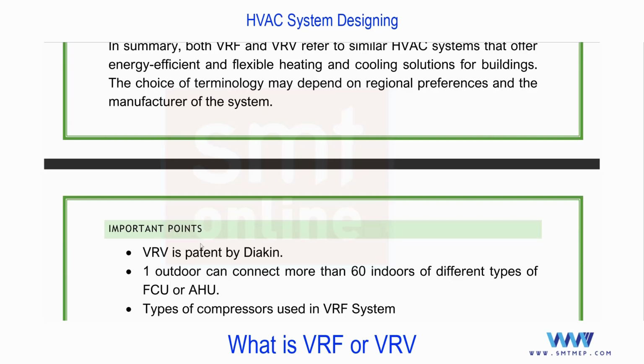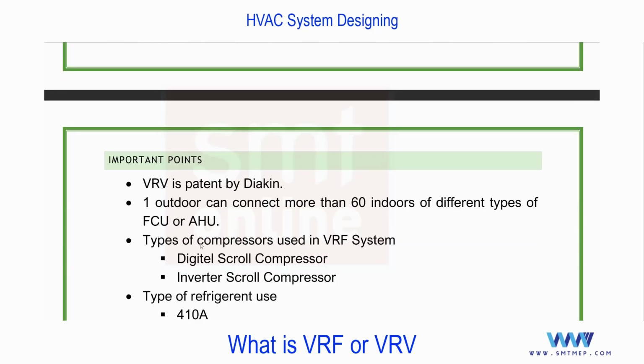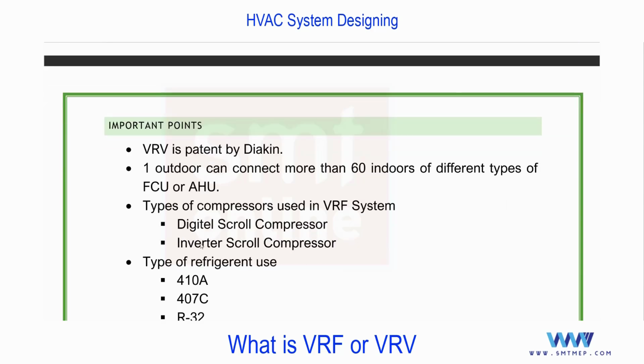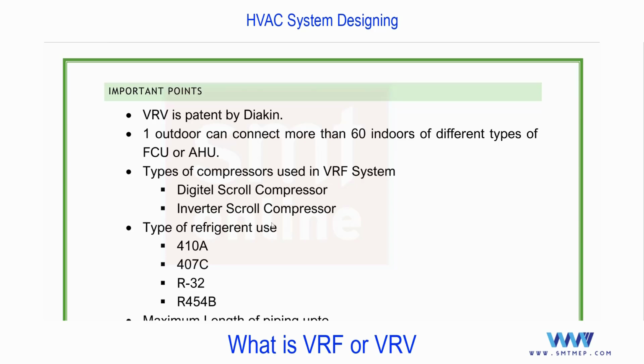Here you see some important points before moving to the different types of VRF. In VRF also you'll find three different types; we'll discuss in detail. As I explained just now, VRV is patented by Daikin, so other manufacturers use the term VRF. From a technology point of view, both are the same. One outdoor can connect to more than 60 indoors of different types of FCU or AHU. An FCU can be a concealed FCU or a decorative FCU, or it can be a floor mounted AHU or a ceiling suspended AHU.